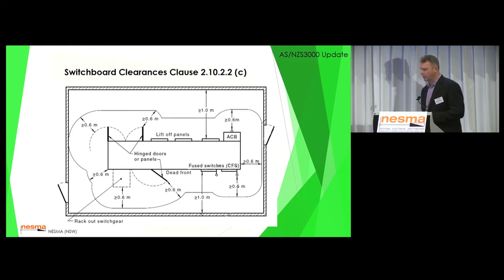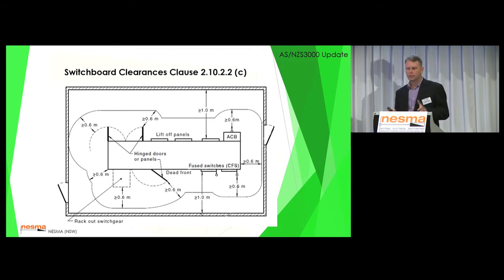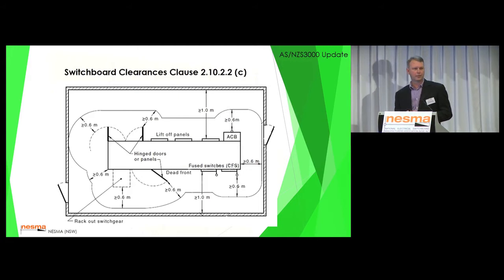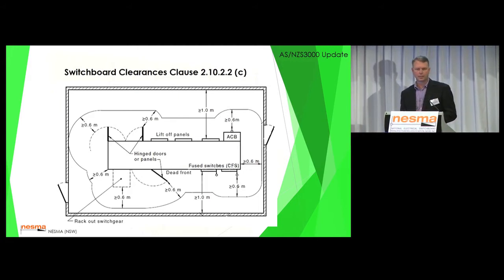So as you can see with this one, we've got 600 from all of the projections as an absolute minimum. 1 metre from the usable face. Now the top right there you can see an air circuit breaker that actually projects beyond that usable face of the switchboard. The 600 clearance, minimum clearance, is from that projection of the circuit breaker. If the 1 metre from the usable face is further than that, then the 1 metre takes precedence. It's a fairly informative diagram.